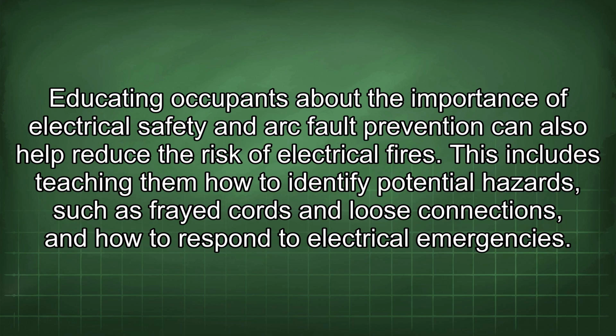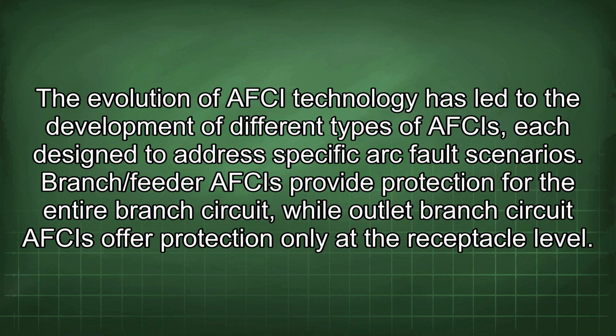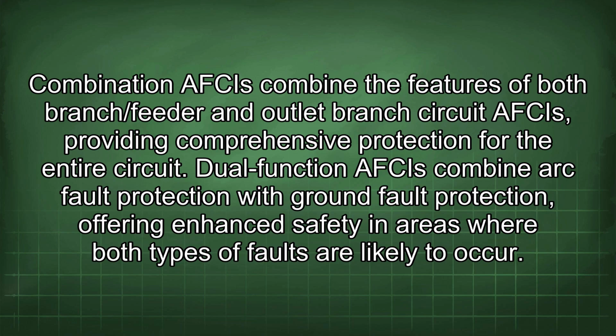to electrical emergencies. The evolution of AFCI technology has led to the development of different types of AFCIs, each designed to address specific arc fault scenarios. Branch/feeder AFCIs provide protection for the entire branch circuit, while outlet branch circuit AFCIs offer protection only at the receptacle level. Combination AFCIs combine the features of both branch/feeder and outlet branch circuit AFCIs, providing comprehensive protection for the entire circuit. Dual-function AFCIs combine arc fault protection with ground fault protection, offering enhanced safety in areas where both types of faults are likely to occur.